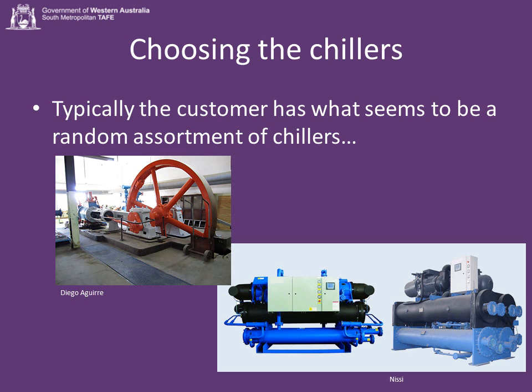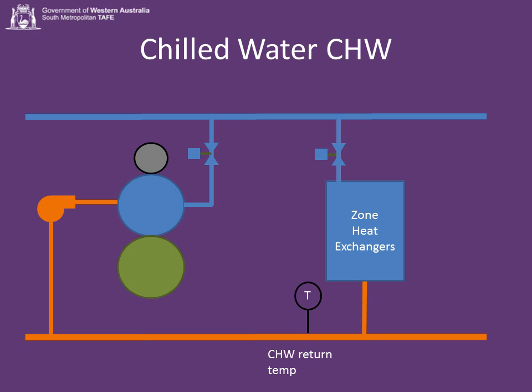Before I go, I want to quickly talk about chillers. Chillers are refrigerators that cool water, and we use that cool water to cool the air. So we generally have in a building, unless it's a brand new building, a right rag bag of assorted chillers from all sorts of different decades. A chiller has two sections. The first section is the evaporator, and what the evaporator does is it gets cold and supplies chilled water.